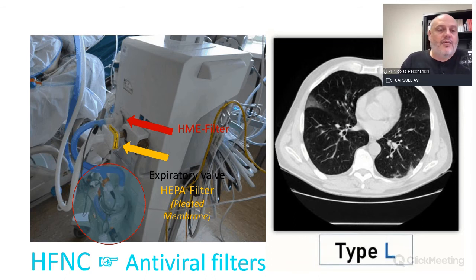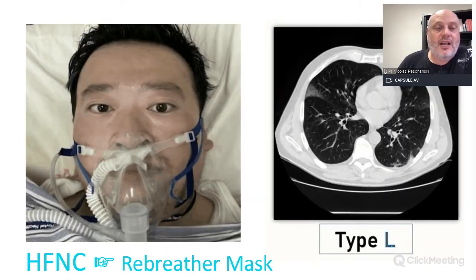So we set some protections to limit the spreading of particles. On the way in to the patient, we put an HME filter, and on the way out, to protect either the ventilator or the providers, we put a HEPA filter that we tested, with very low spread of particles using this device.